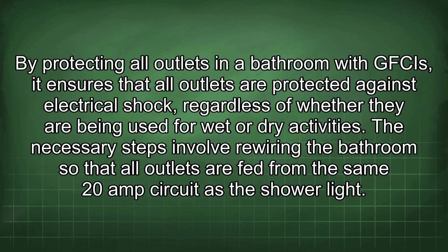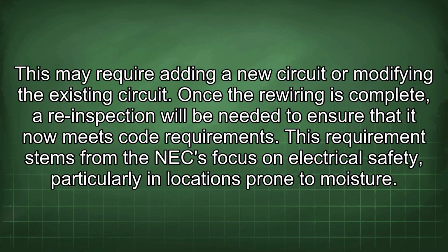The necessary steps involve rewiring the bathroom so that all outlets are fed from the same 20-amp circuit as the shower light. This may require adding a new circuit or modifying the existing circuit. Once the rewiring is complete, a re-inspection will be needed to ensure that it now meets code requirements. This requirement stems from the NEC focus on electrical safety, particularly in locations prone to moisture.